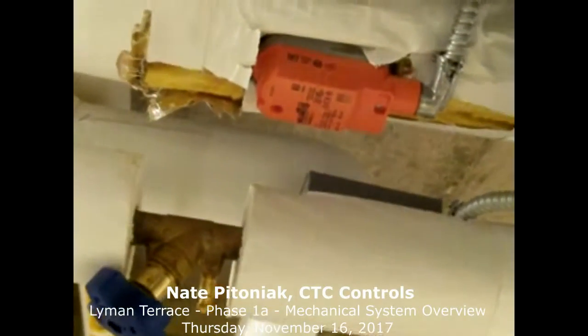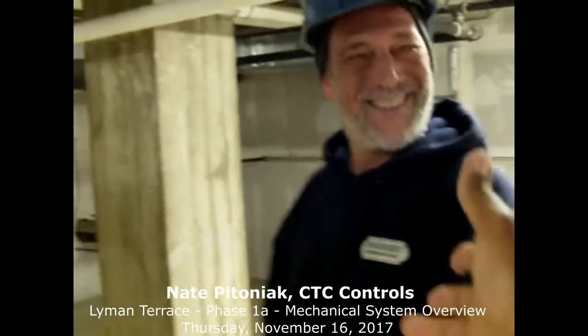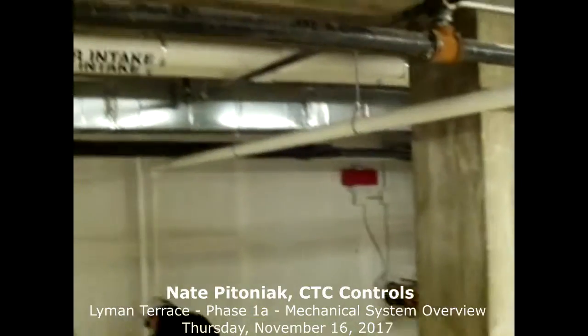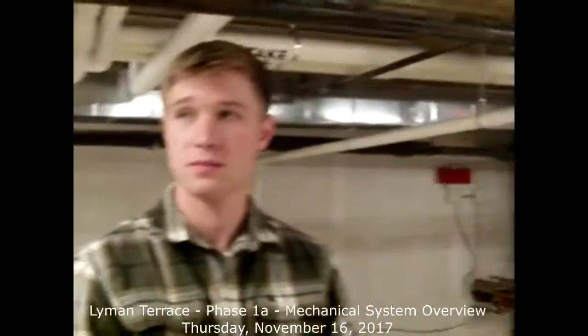So this is the same Belimo actuator that's in each apartment? Correct. In an emergency, we can steal the head off. These are really good. Now, these were built with service in mind. If you ever have to service them, just grab the head itself and give it a good pull. That just pulls off? Yeah. And it's not going to leak when you do that. Once you get your new one, you pop it on, reattach your wires, and walk away. So having a few extra of those wouldn't be a bad thing. No, it would not.